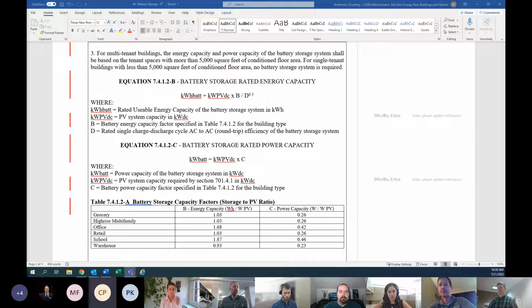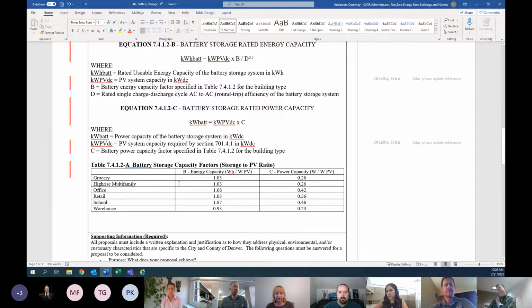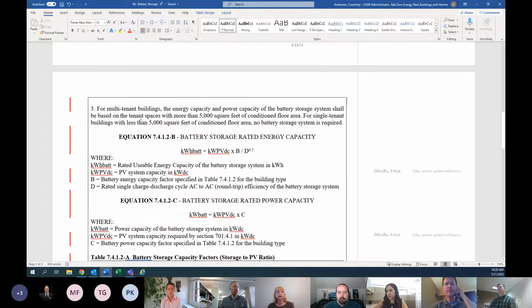Hi, John. I have a question. This is Carol. I'm hoping you can help me to understand the exceptions, because I was looking at the third exception, last sentence: for single tenant buildings with less than 5,000 square feet of conditioned floor area, no battery storage system is required. So my assumption is, if it's 5,000 and above, it would require a battery storage system. That's at least how I see it.